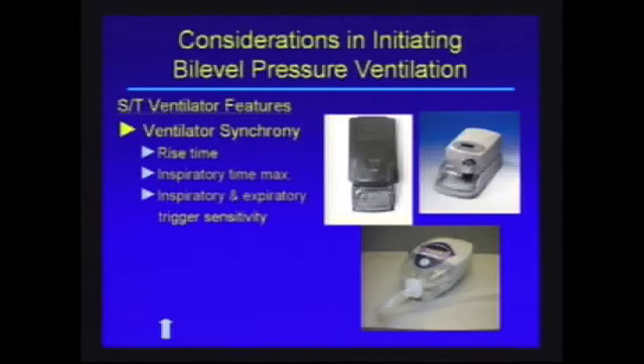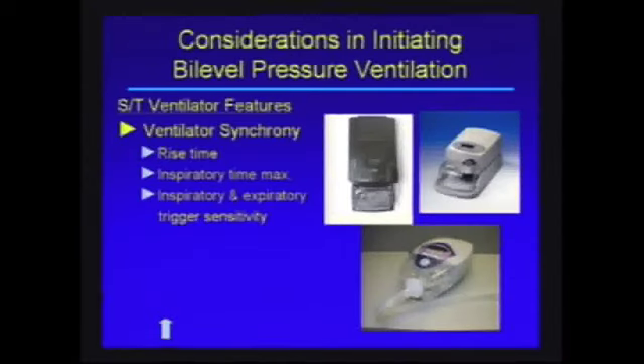So different types of settings, or what we call parameters, can be adjusted in order to do that. One of them is rise time. That's the transition time from the exhalation pressure to the inspiratory pressure. We want to make sure that it's in sync with your breathing. How fast do you want that machine to respond to you relative to when you breathe in? We all have a particular breathing pattern, and some of us want that inspiratory pressure on that IPAP to come to us a little bit more gradually, and others of us want it to come quickly. So this is a very important thing that needs to be adjusted relative to what you feel is comfortable, and that's the key. It's what you feel is comfortable because you are the user, and when a person is set up with this, it needs to be addressed.